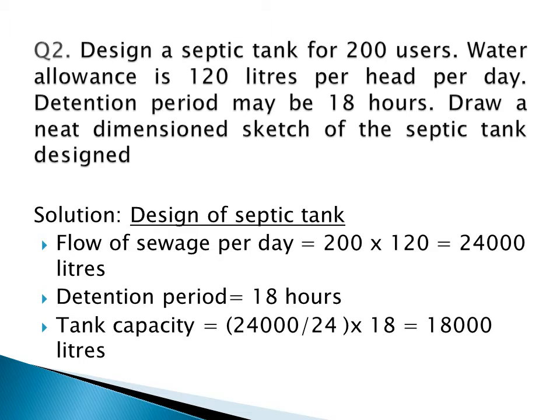The first step is to find out the flow of sewage per day. Per person, the water consumption is 120 liters per head per day. For 200 users, it is 200 multiplied by 120, which equals 24,000 liters. Converting to cubic meters by dividing by 1000, we get 24 cubic meters per day.